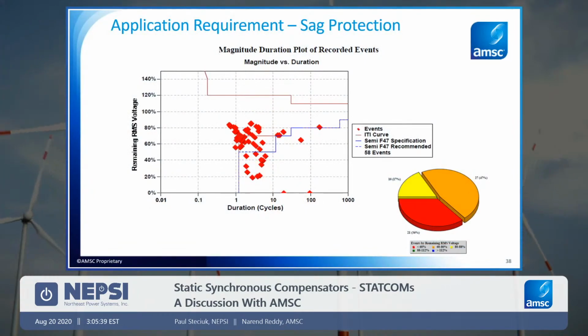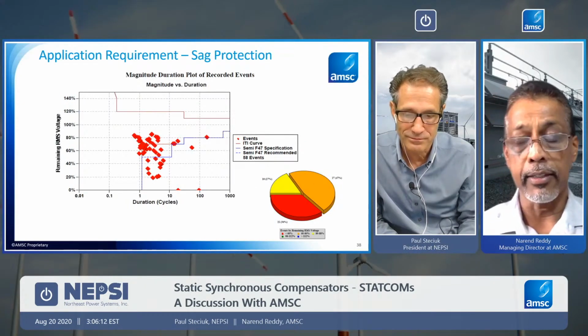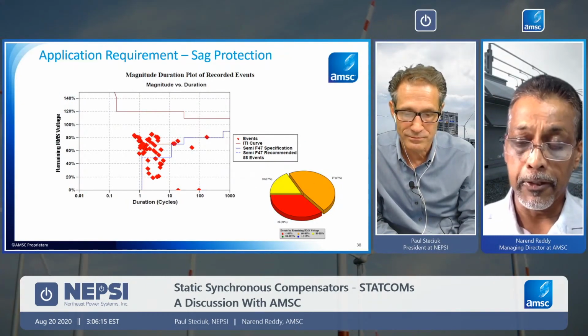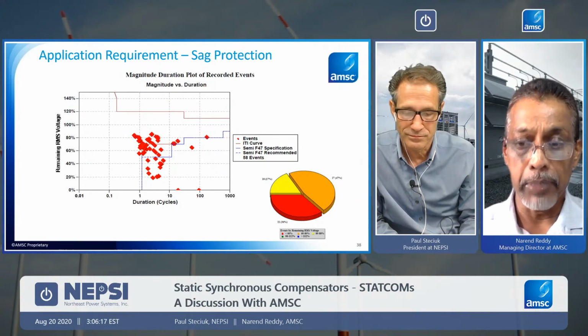as you can see in this facility, this is basically a record of all of the sags that this particular facility experienced, and it shows you that there are a significant number of sags that are outside of what would be considered acceptable for the tools to ride through. So that means the tools in this particular facility are being affected, and the intent really would be to provide sag protection or rebuild very, very quickly, so that these sags do not fall outside of these thresholds, and the amount of damage or downtime to the facility is minimized.